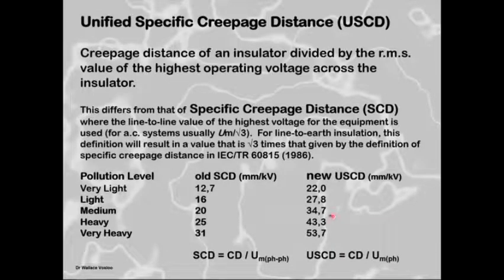And if we go on to confuse things and make things quite interesting, they brought in something new, which is called unified specific creepage distance, where we used to use specific creepage distance. Now, specific creepage distance is basically where you take that creepage distance where the lazy ant has walked over the surface, and you divide it by the RMS value of the highest operating voltage across the insulator. So in the old days, they would take your creepage distance and divide it by U max phase to phase. So normally you would have ordered a 16 millimeters per kV insulator, or a 25 millimeters, or a 31, depending on your pollution level in your area.